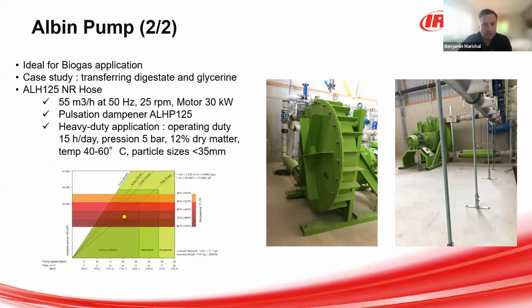You can see on the right picture a pulsation dampener to prevent the installation from hammer effect. So it will help reduce the total cost of ownership. And this application is typically 15 hours a day, with a back pressure of 5 bar. And we are handling 12% dry matter at 40-60 degrees temperature with some particles with size below 35 millimeters. So that's a typical application transferring digestate with this ALH series pump.